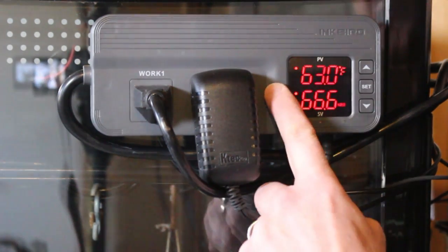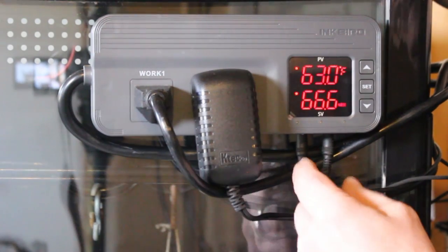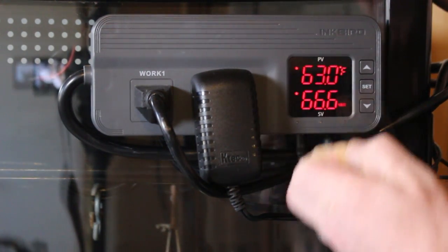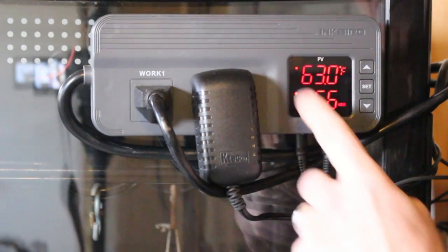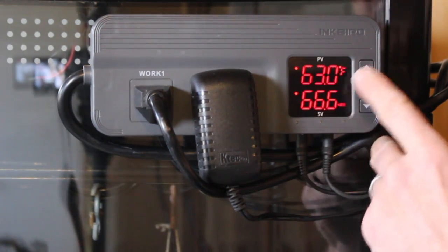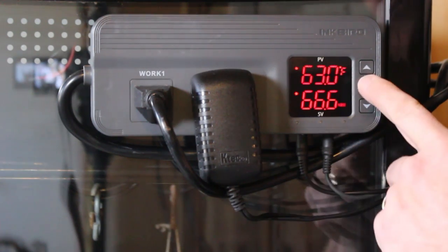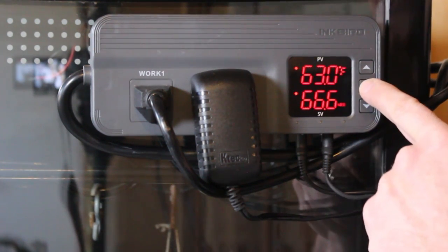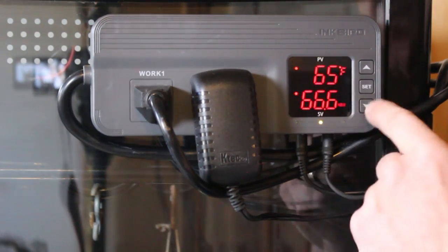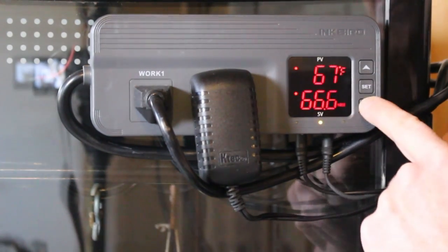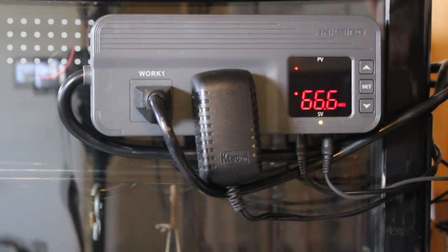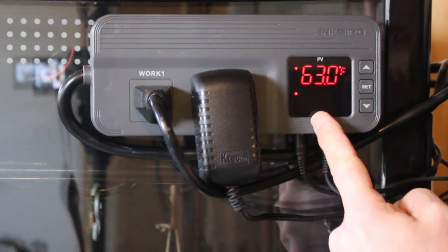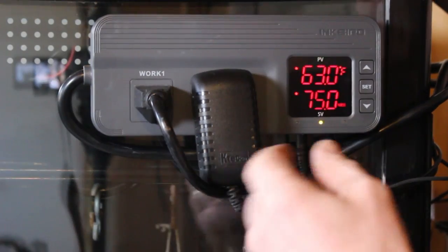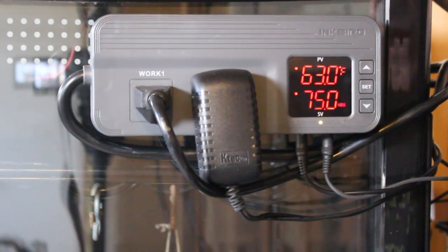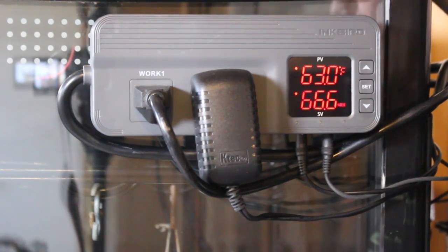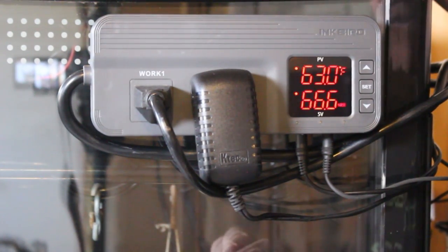So essentially, you can see here the normal readout is, well, here I've got the shipping plastic on there. It always irks me when people leave stuff like this on their electronics. The normal display is the temperature in Fahrenheit and then the relative humidity. If you want to make a quick change to that, you just hit the set button. And you can change, maybe I want to turn it up a couple of degrees or turn it down a couple of degrees. Hit the set button again. Here you can see my set point is 75% relative humidity, meaning that when the amount of water in the air relative to the temperature increases over 75%, it'll turn on my dehumidifier.